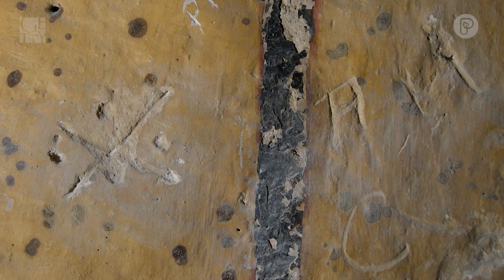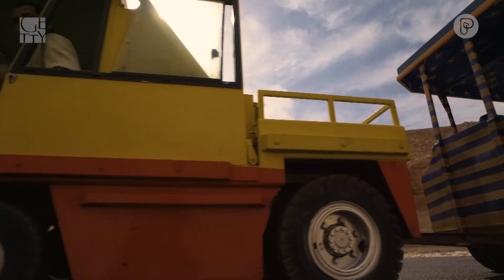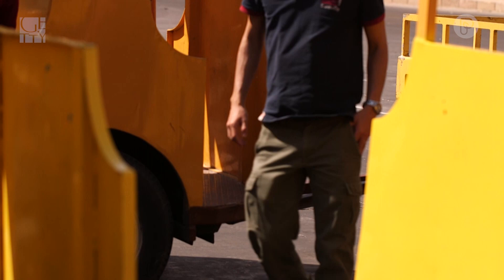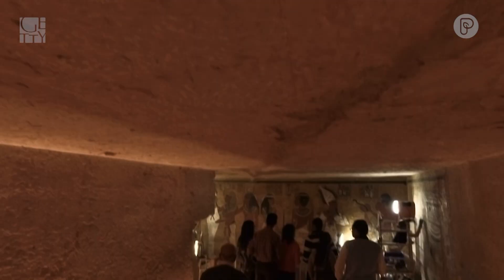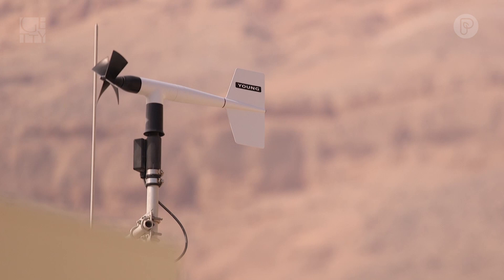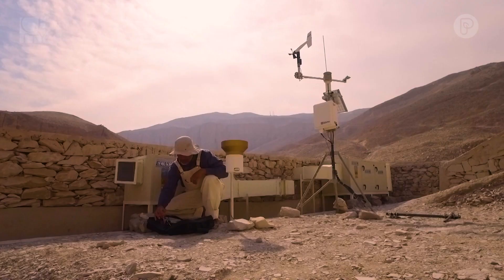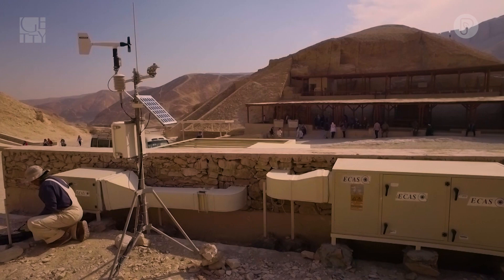Adding a filter to the ventilation system helps filter out the dust. There's also modern graffiti and physical damage due to film crews who come in with cables and lights in a great hurry. There's dust intrusion coming in with visitors on their clothes and shoes, and potential indirect effects in terms of altering temperature and humidity, raising humidity levels and impacting the delicate original technology of the paintings. The installation of the new ventilation system was designed to prevent this. We installed a push-pull system so that we're actually bringing in filtered air and extracting it, ensuring that any air brought in when visitors arrive is now filtered so we're not encouraging as much dust from entering the tomb.